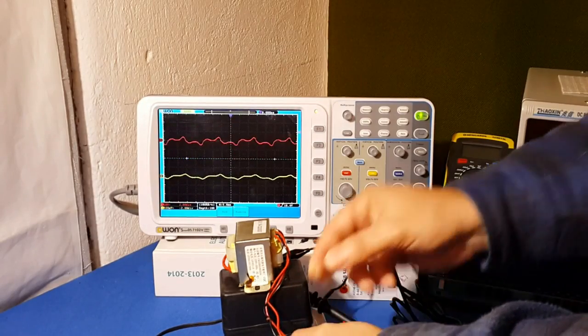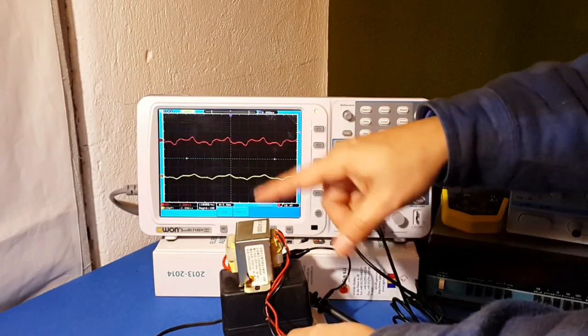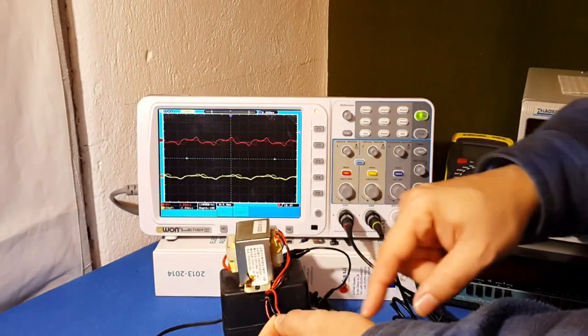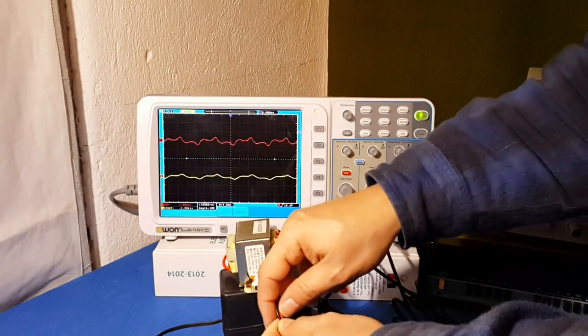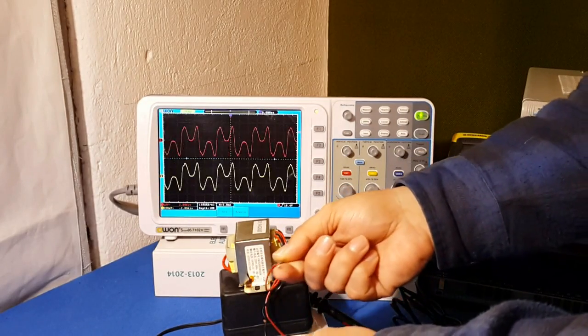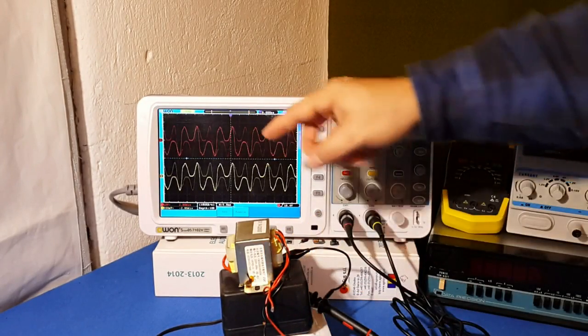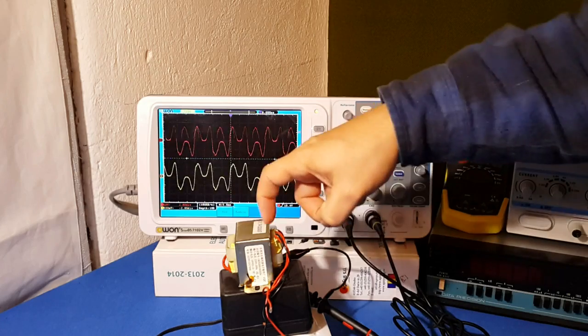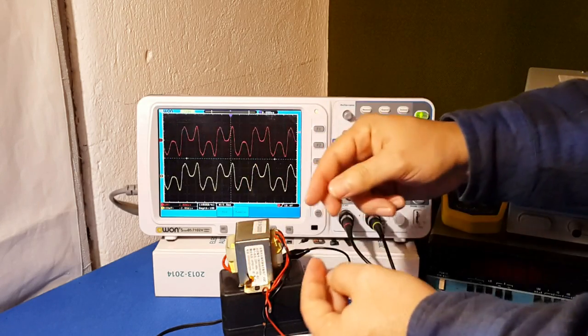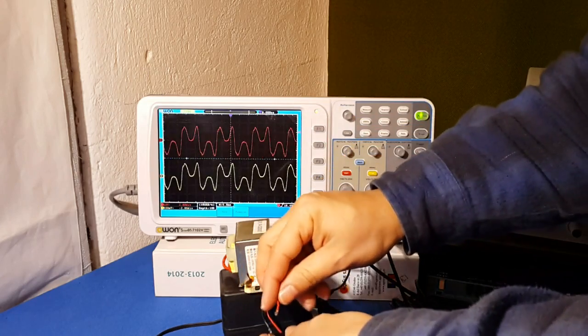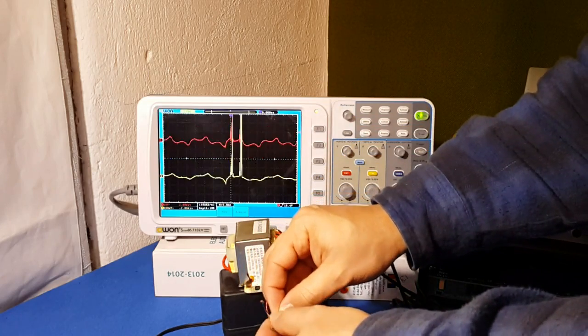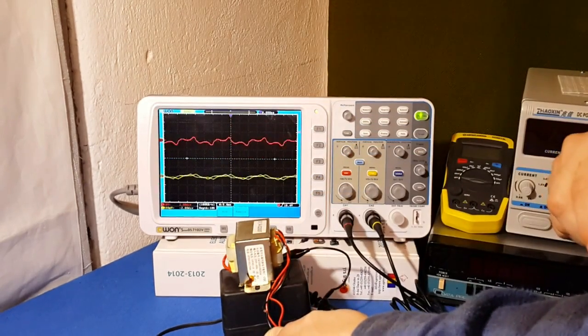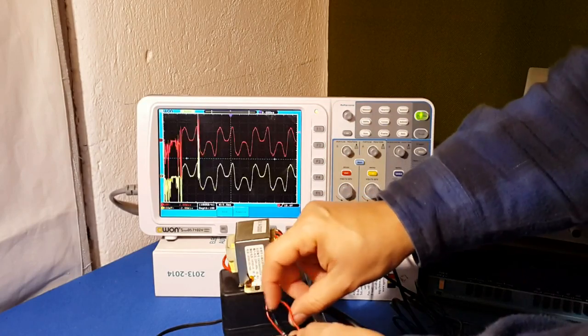The voltage is dropping. Why is the voltage dropping down, falling? Because I have a short circuit. So if I don't get voltage, that means I have an open winding—one of the reasons—or I could have a short circuit in one of them.